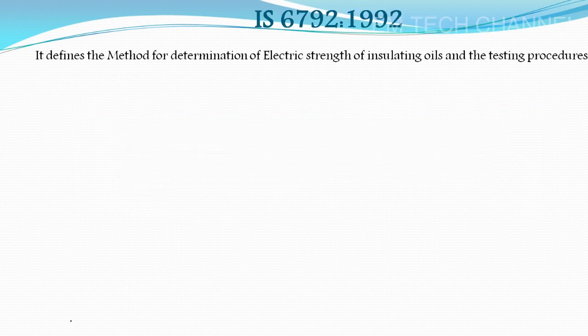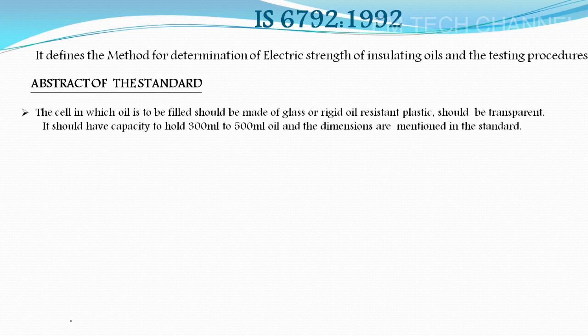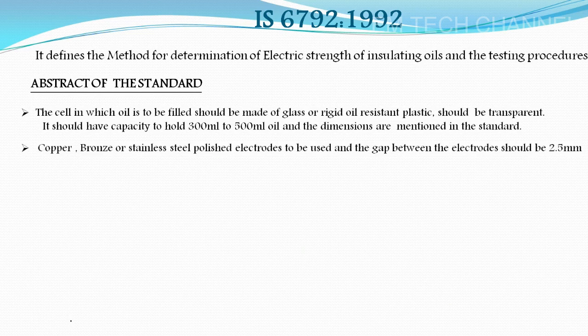And next we will see IS 6792 and the abstract of it. It defines the method for determination of electric strength of insulating oils and its testing procedures, and the abstract of the standard is the test cell in which the oil is to be filled should be made of glass or rigid oil resistant plastic and should be transparent, and it should have capacity to hold the volume of 300 ml to 500 ml oil, and the dimensions are mentioned in the standard.